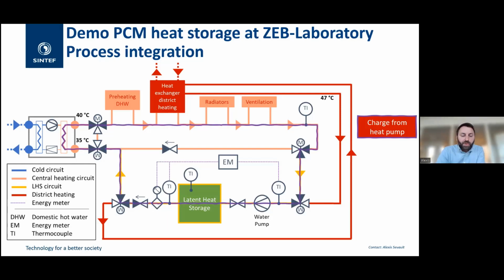This is how it looks: we run the heat pump, the hot water goes out at 40 degrees, and let's say the consumers - preheating of domestic hot water, radiators, ventilation - don't need much because it's a warm day, or it's not too cold, or they've already warmed up the building. So the water keeps running at 40 degrees and we deviate it towards the latent heat storage, the green box, and melt the PCM with water above 37 degrees. With the system we developed, 2 to 3 Kelvin above the melting temperature is enough to effectively charge the latent heat storage. That's quite interesting - we don't need 5 or 10 degrees above, just 2 or 3 Kelvin, and it works quite effectively. So that's one way to charge.